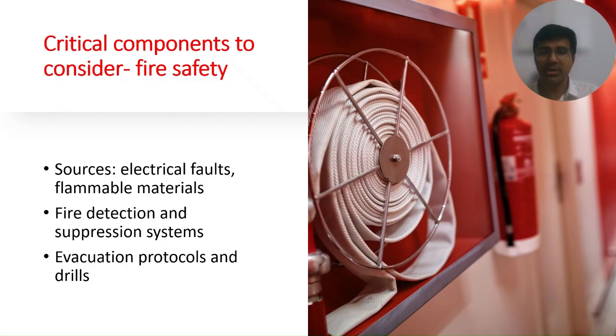So current suppression systems are being turned more into non-water based systems. Inside the OT they also have non-water based suppression systems, like clean agent systems of inert gases or inert components like FM200 or Novec 1230, which does not spoil your equipment. This can be thought about.